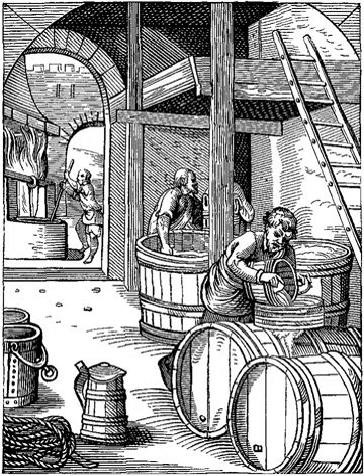Pre-made filters have two sides, one with loose holes and the other with tight holes. Flow goes from the side with loose holes to the side with tight holes, with the intent that large particles get stuck in the large holes while leaving enough room around the particles and filter medium for smaller particles to go through and get stuck in tighter holes. Sheets are sold in nominal ratings, and typically 90% of particles larger than the nominal rating are caught by the sheet.